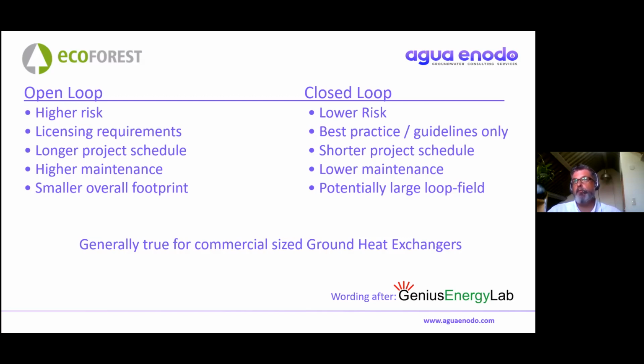Obviously then we have the pipe run to and from the plant room, but the footprint can be very small. And because the flow rates from a single borehole can be quite high, we've got some systems that operate at 50 liters a second. Obviously the thermal capacity of a single borehole or borehole pair can be a lot higher for the same rate that you'd get from a closed loop field.